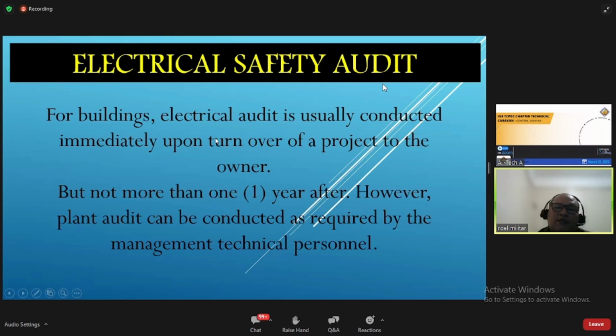For buildings, an electrical audit is usually conducted immediately upon turnover of the project to the owner. Okay, so this is the process. After it is turned over, an electrical audit is conducted based on what is in the design. So it should be upon the turnover of the project, but not more than 1 year after. However, the plant audit can be conducted as required by the management technical personnel. So if the management technical personnel need to conduct it, then it's a must, no? It's necessary also to conduct an electrical audit.